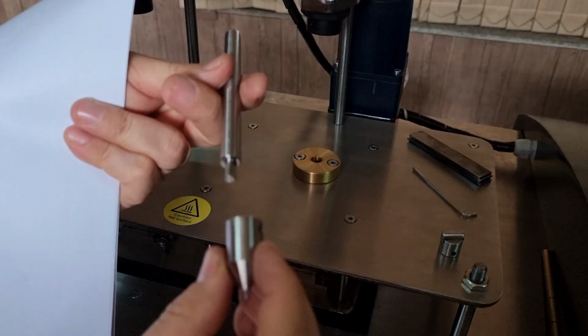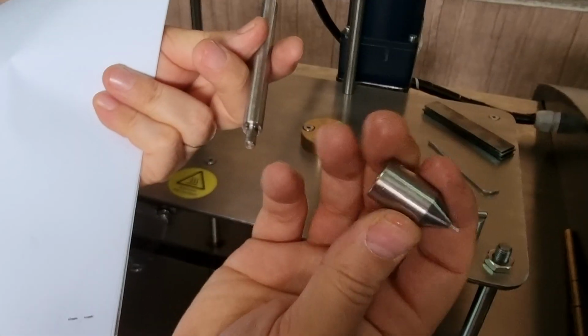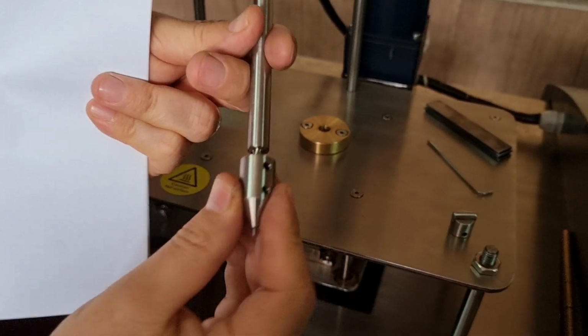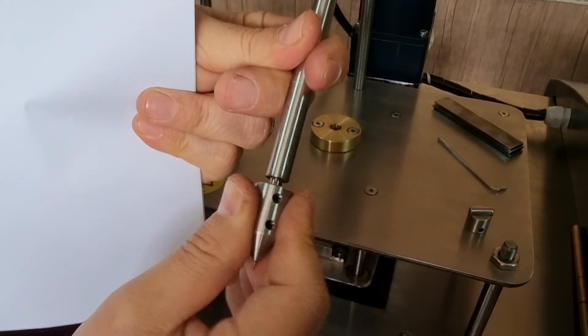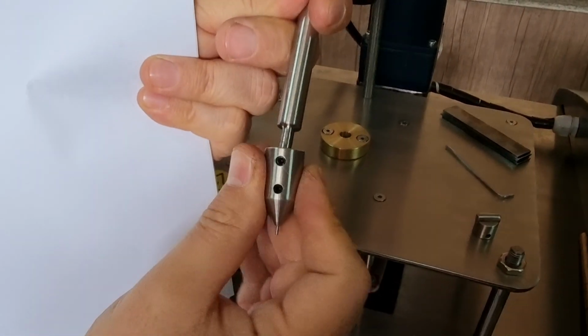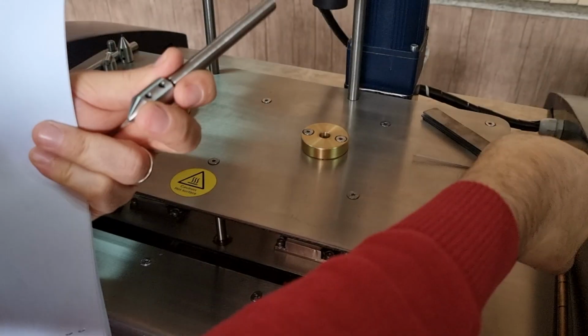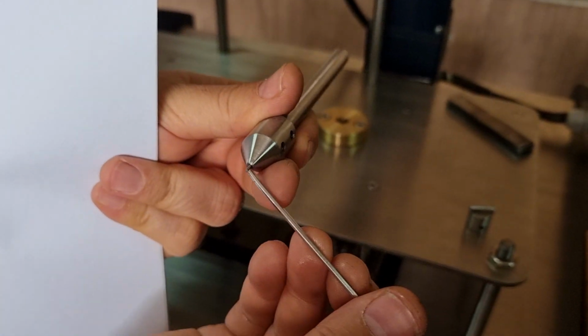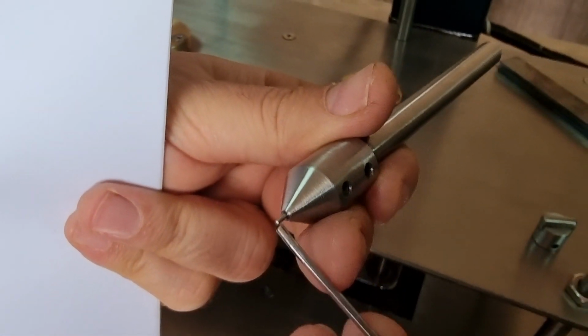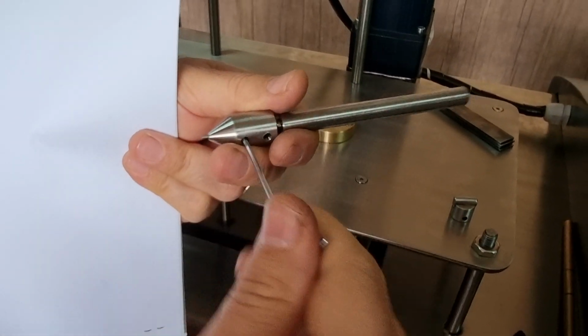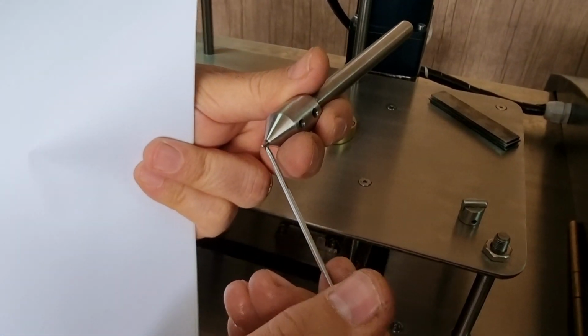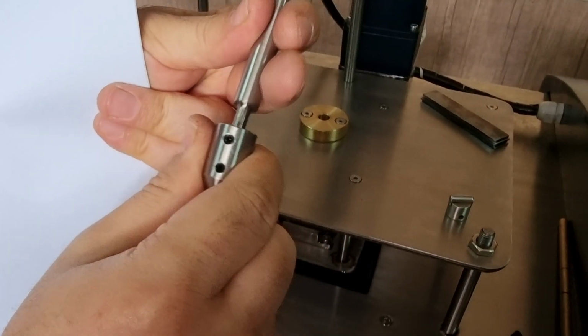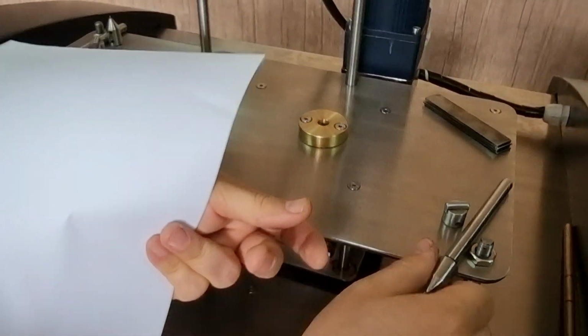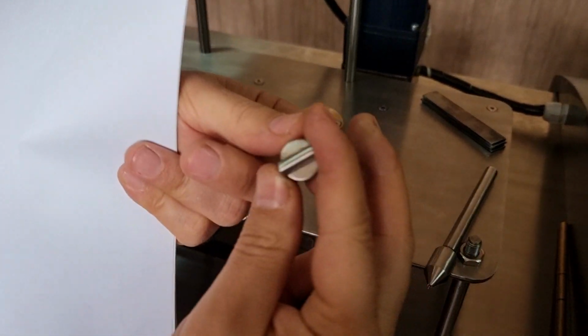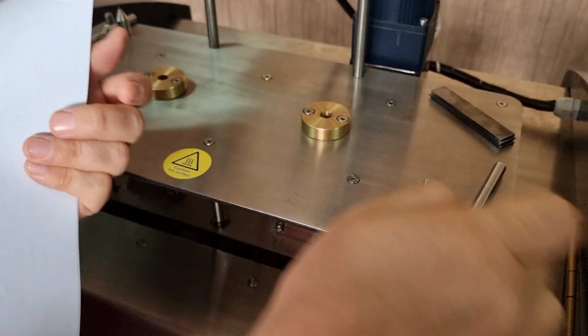You have the rod. The two types of heads for Vicat is this one. This is the head for Vicat testing, and you need to put it here to install on the rod, like this. You can also open and change the needle easily. The cross section of this needle is 1 millimeter square as per standard. You can easily open this set screw and change this Vicat needle. Also, you have another type of head for HDT testing, heat deflection temperature. You can easily change it.